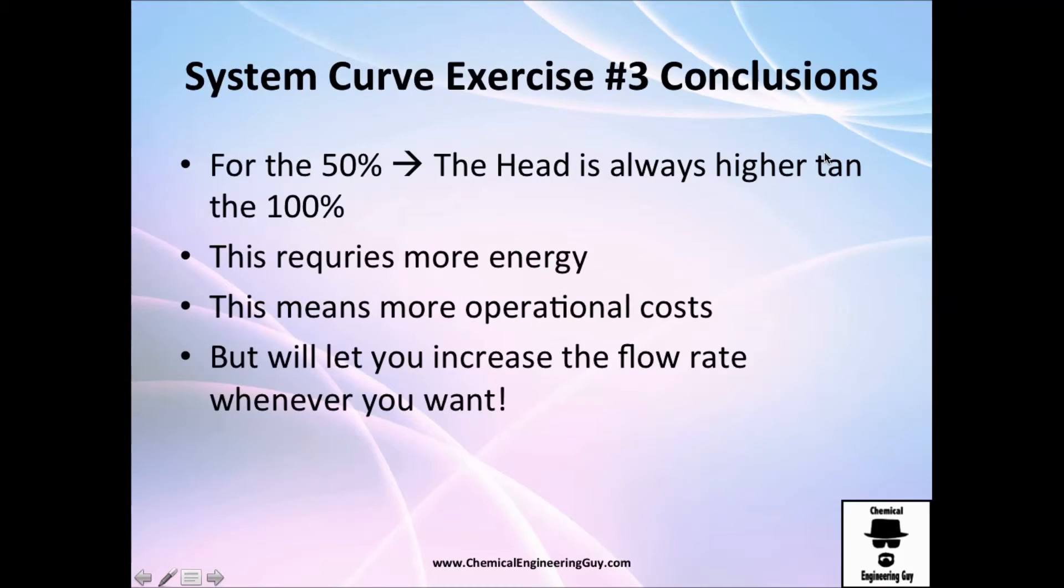Essentially, if you increase friction or you close the valve, you increase the head, which means this will be always over the one of the hundred percent. Doing this requires energy, of course - more energy drop or friction loss will require more energy. This means we're going to lose a little bit more money on the operation cost.